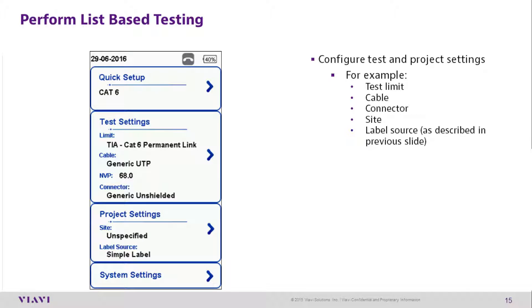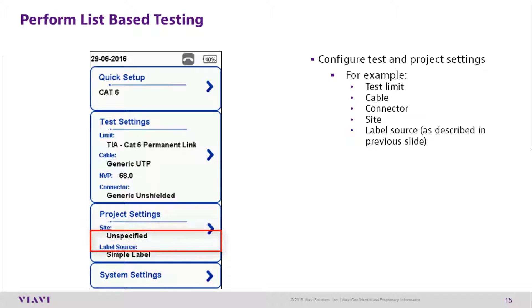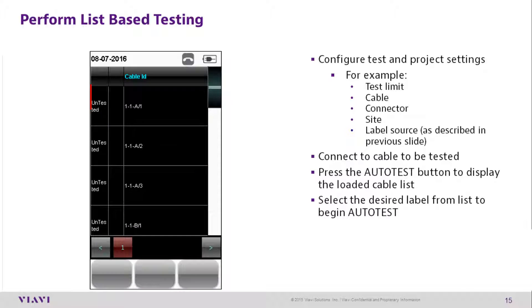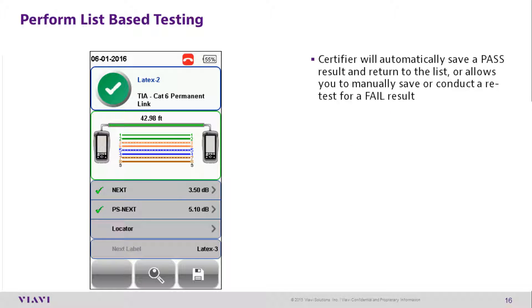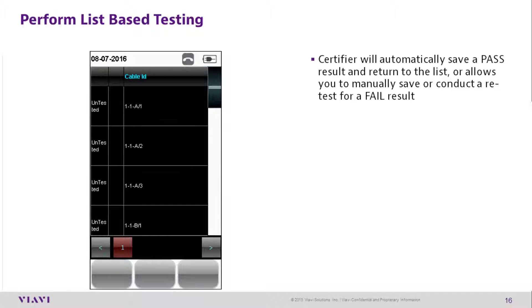To perform list-based testing, configure the test in Project Settings — for example, set the test limit, the cable and connector being used, the site, and the label source. Connect to the cable to be tested and press the Auto Test button to display the loaded cable list. Select the desired label from the list to begin auto-test. The certifier will automatically save passing results and return to the list, or allows you to manually save or conduct a retest of failed results.